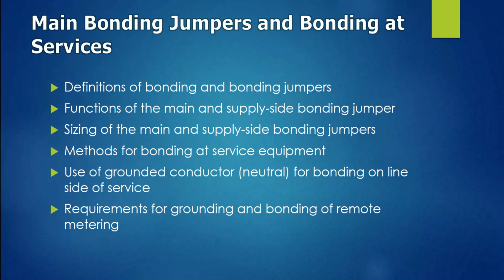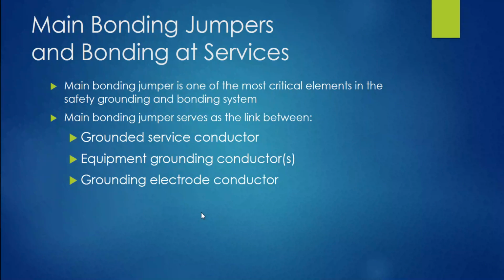But I guess it could apply if it's an underground service lateral that goes over to a pad-mounted transformer that is actually owned by the premises. Then all of that is still service conductors if we're dealing with a utility-type transformer. And then, of course, we're going to look at the requirements for grounding and bonding of remote metering.